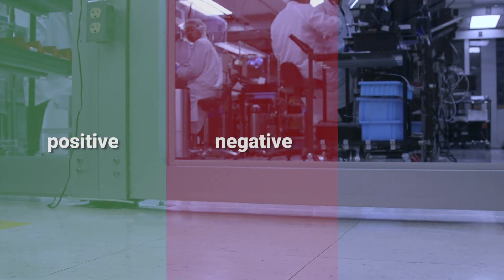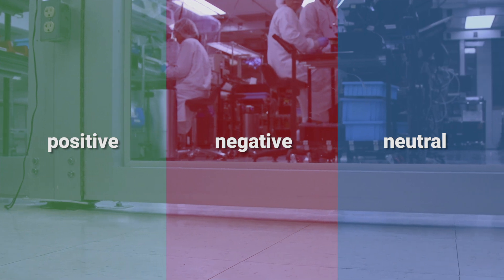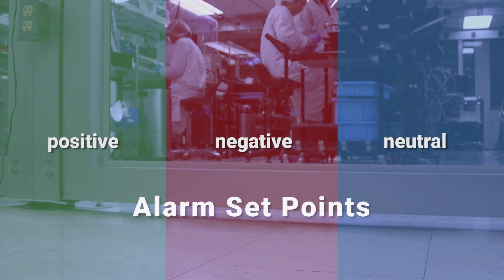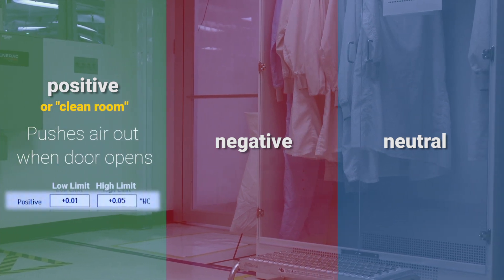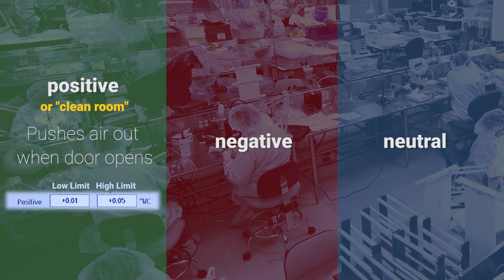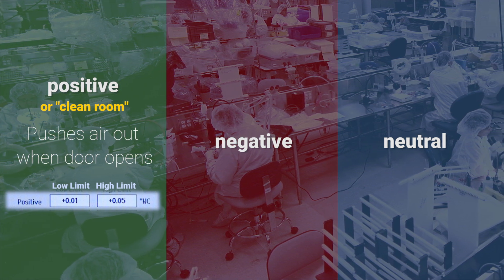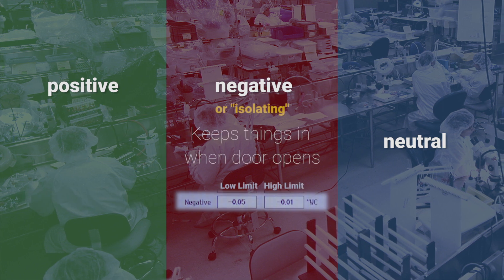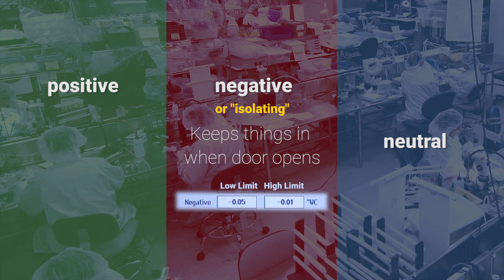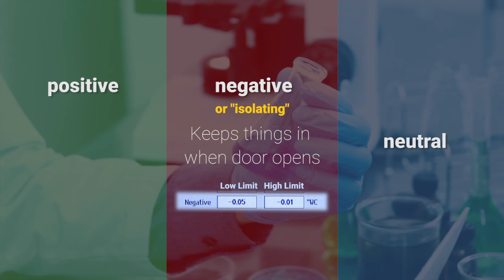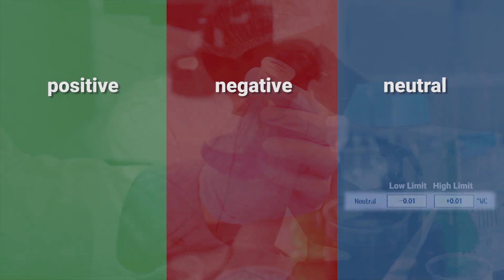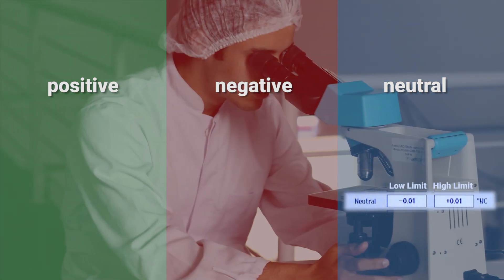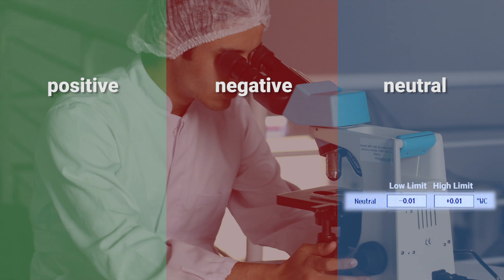For critical environments, the space being monitored can be a positive, negative, or neutral space. The user determines what kind of space is monitored with the alarm set points. A positive room will have an alarm set point slightly above zero differential pressure to some greater positive pressure. A negative pressure room will have alarm set points from less than zero differential pressure to a deeper negative pressure. A neutral room will have the high alarm set point in the positive pressure range and the low alarm set point will be a negative number.